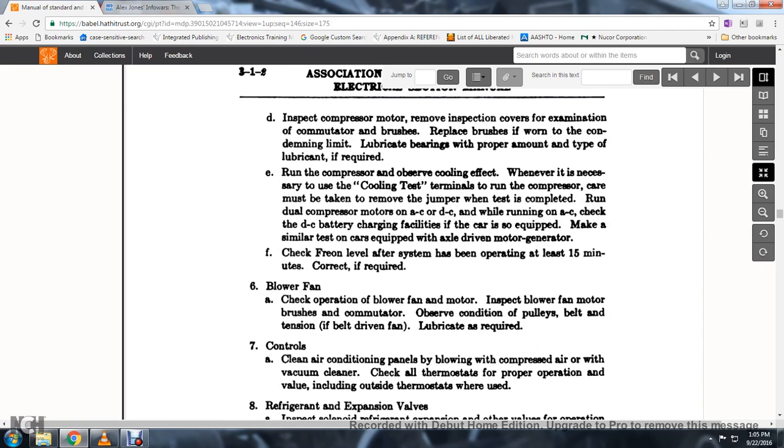16. When inspecting the compressor motor, remove the inspection covers for examination of the commutator and brushes; replace brushes if worn to the condemning limit. Lubricate the bearings with the proper amount and type of lubricant if required. Run the compressor, observing the cooling effect.